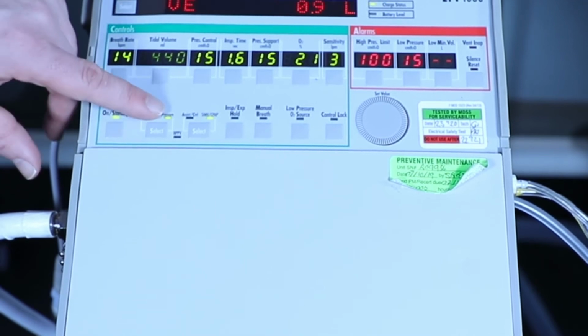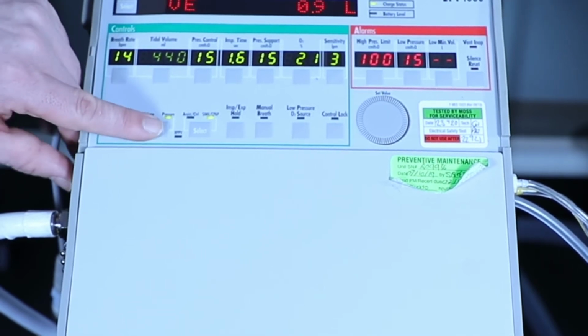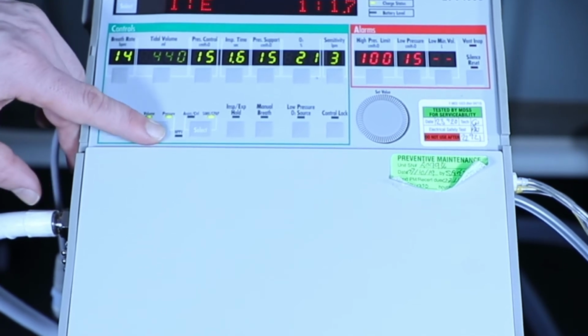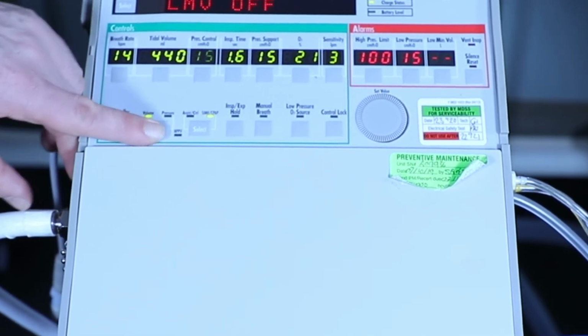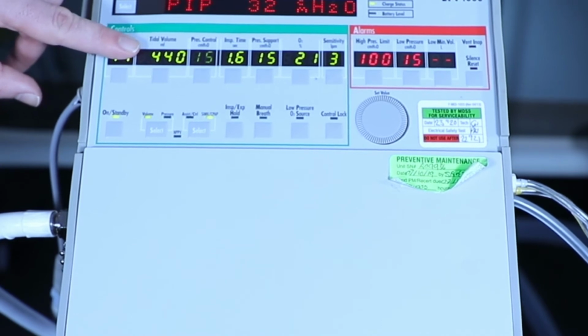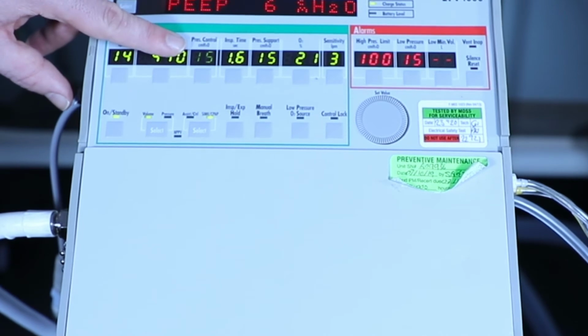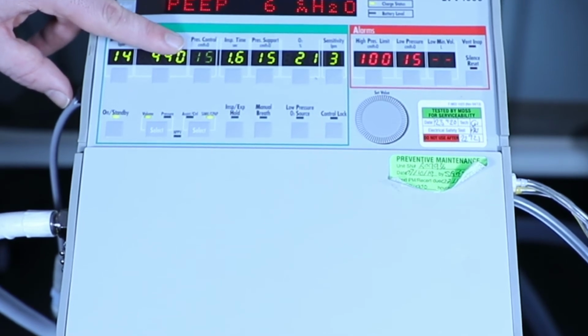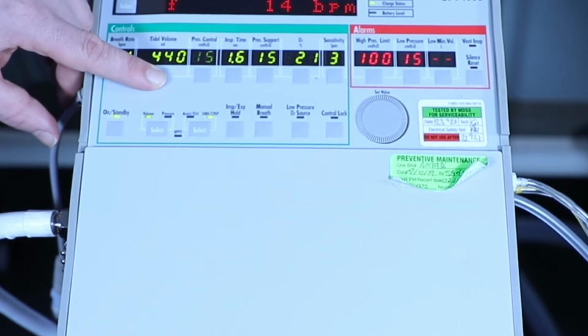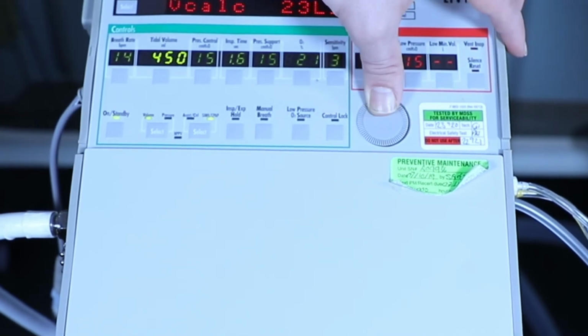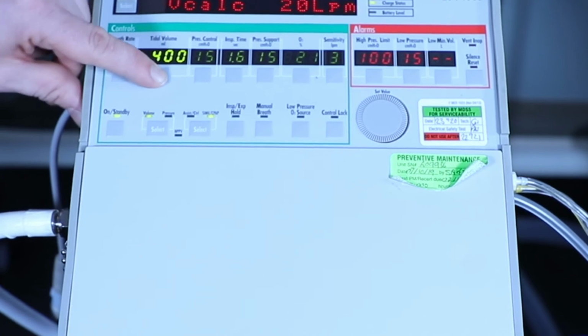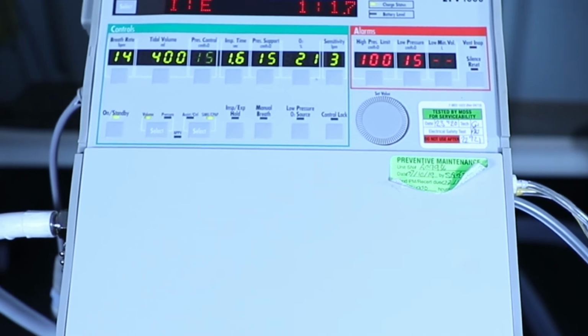Here we have the volume or pressure selection, so if we want to change between volume and pressure, we press, you can see we're on pressure. If we press once, volume flashes, press again to confirm, and we're now in volume mode. We also notice that the tidal volumes become brightly lit and the pressure control becomes dim lit. So if we wanted to change the tidal volume now, we can press, use our jog dial and press to select. Tidal volumes for this mannequin won't be accurate because this mannequin isn't set up to take ventilation.